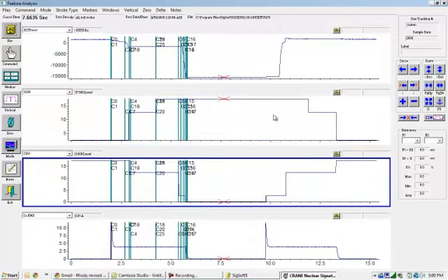Okay, again, we look at the trace, and we can see qualitatively the motor start and motor run. In the closed switches, we have the closed torque switch making up, the red light turning on, and the closed torque switch bypass making.